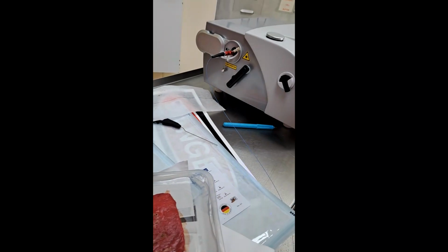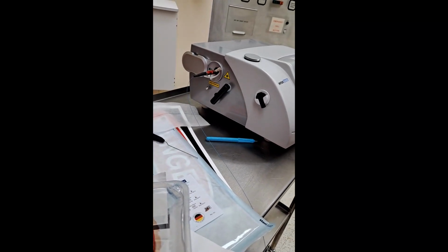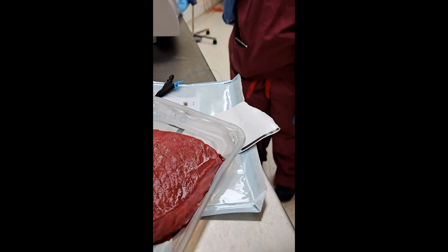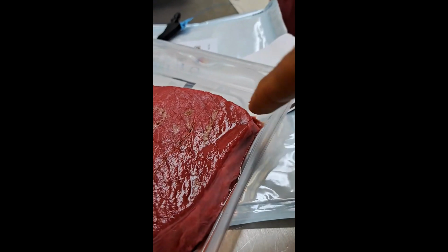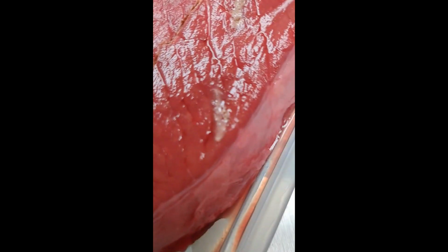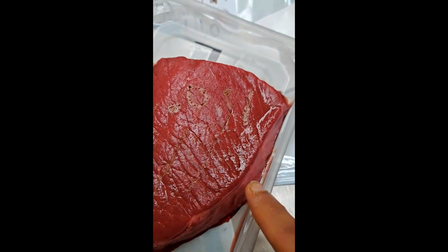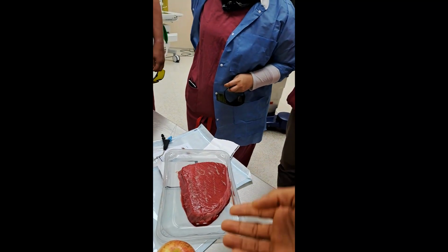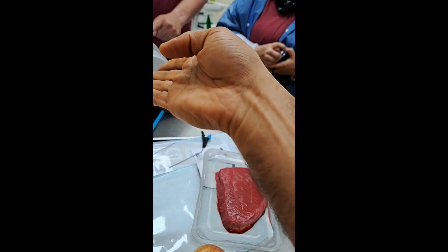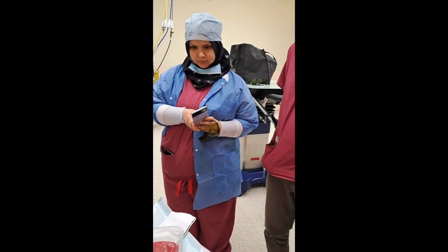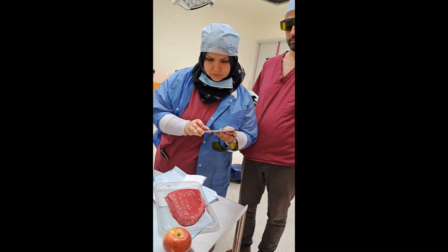And just please stand by, laser stand by, please. Yeah, so laser stand by, and you can see the difference. You can take your goggles now, and you can see the cutting is really sharp, and this is the coagulation effect, which is nicely there. And this is what you need to do. Just try to cut using the cutting or the coagulation. Just make sure you wear the right goggles, yeah.